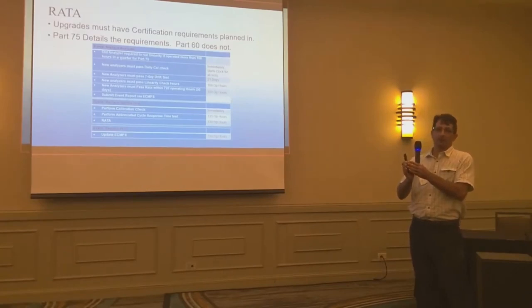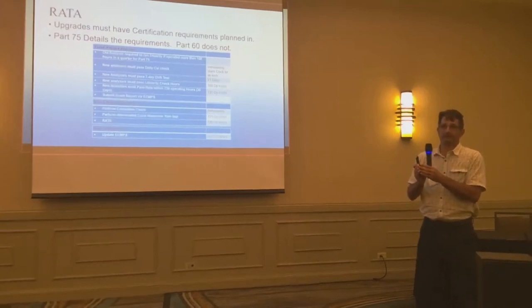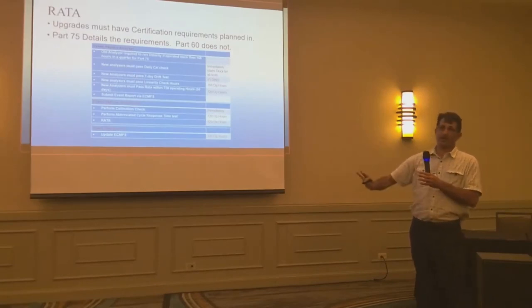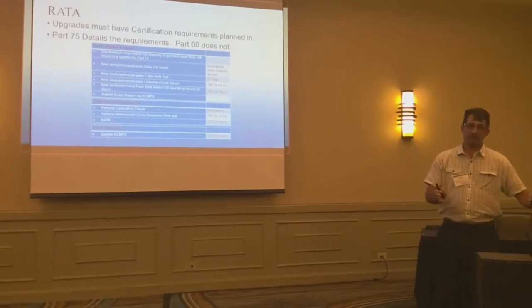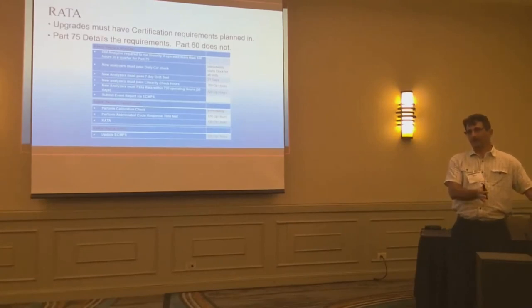Did you do a QA on those? Did you do your quarterly linearity? Because you've got to put a new analyzer in in August. That new analyzer is going to get these tests, so it's all set. But what about all the data from the time that third quarter started up to the point you changed the analyzer? Is that data QA'd? We think it's not. That's our interpretation.